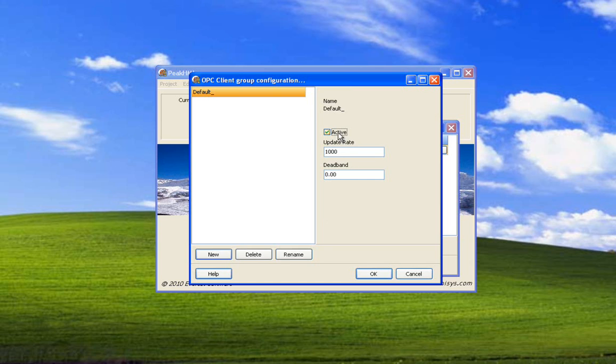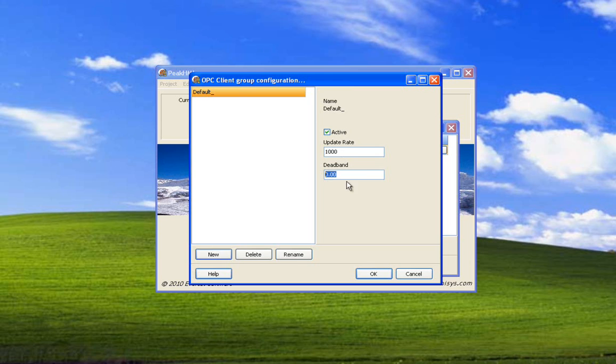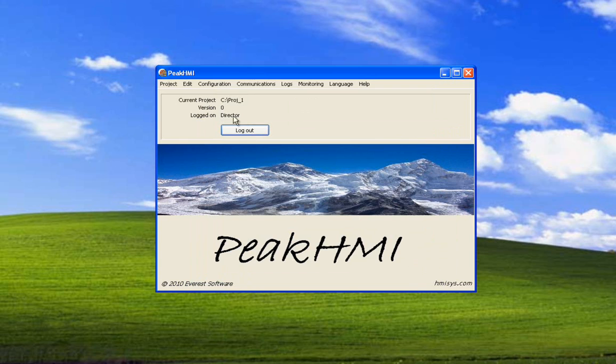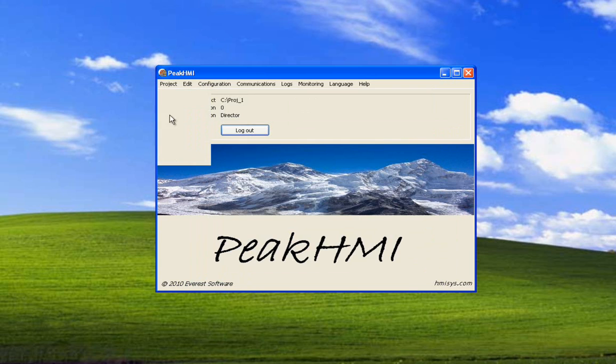We do want to have to set it active. This update rate has to do with the server sending information to the client periodically. Changes to values that are outside the range of this dead band are reported by exception. So we'll just leave it at a thousand. Select OK. Now our server is set up. Select OK. Save the project.